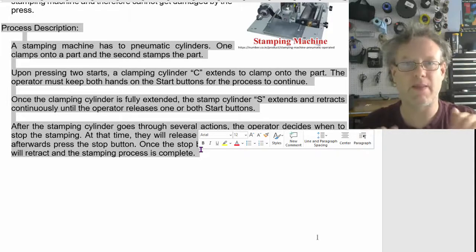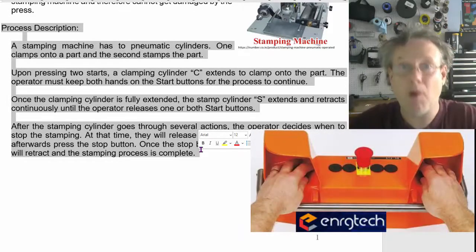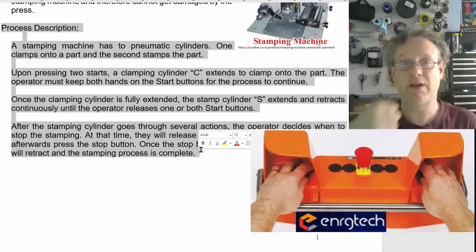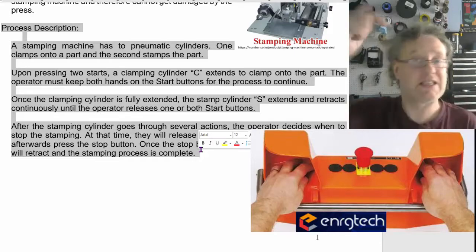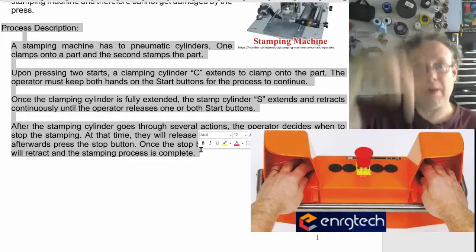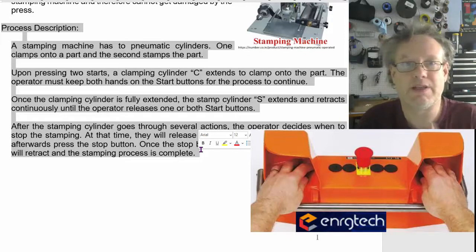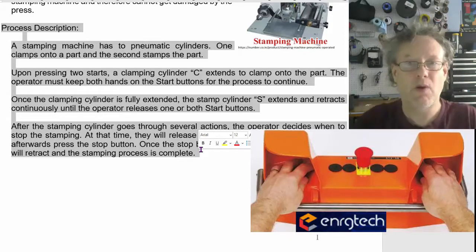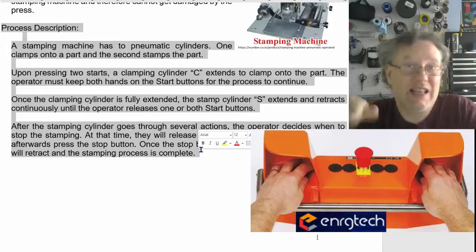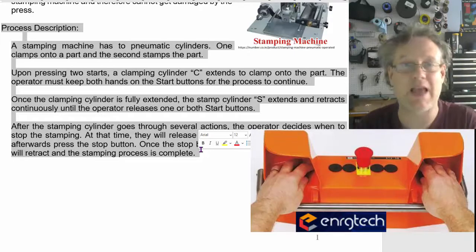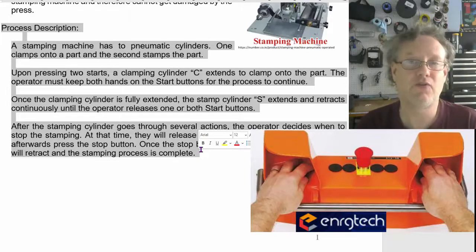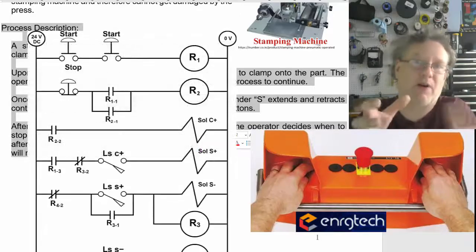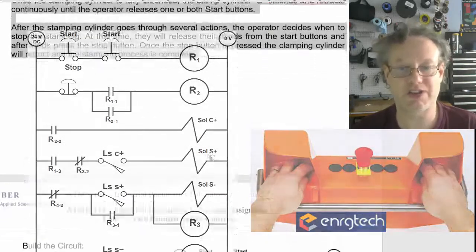What's going on is that the operator goes and puts two hands in, make sure that both buttons are pressed. Then a clamp comes out and I'm calling the clamp in this case cylinder C, and then the stamp goes repeatedly bang, bang, bang, up and down and up and down and up and down. Now that is going to be cylinder S for stamp. When the operator takes his hands outside or stops pressing actually either button, then what's going to happen is the stamp will stop stamping, but the clamp will actually stay clamped for the operator to release the clamp because the clamp is clamping onto the part, right? He has to press the stop button. There you go.